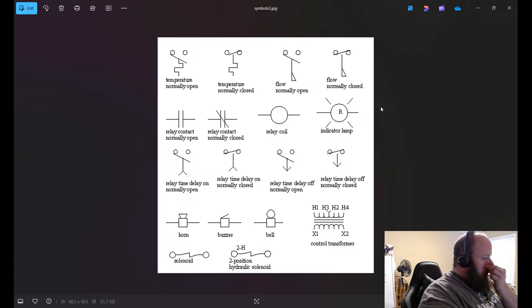As you can see how the icons are written. Now, the biggest thing is relay time delay on normally open. And that's delay on, so the arrow faces up. Delay offs are arrows facing down. Don't get those confused. They're like that for a reason.